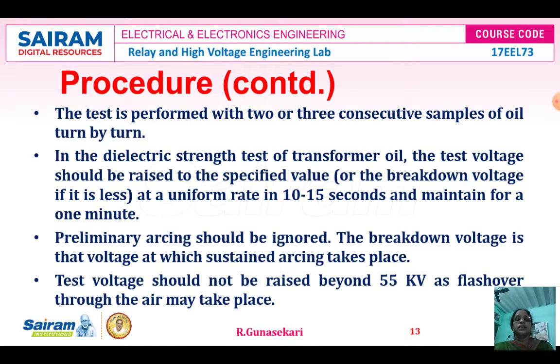In the dielectric strength test of the transformer oil, the test voltage should be raised to the specified value, or the breakdown voltage if it is less, at a uniform rate in 10 to 15 seconds and maintained for 1 minute. Preliminary arcing should be ignored. The breakdown voltage is the voltage at which sustained arcing takes place. Test voltage should not be raised beyond 55 kV, as flashover through the air takes place.